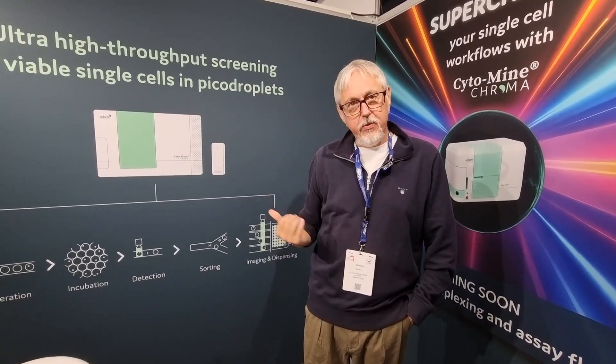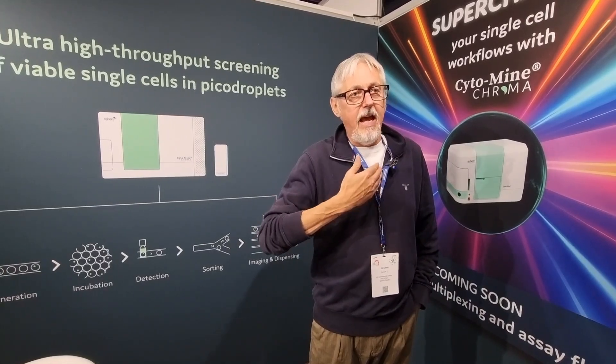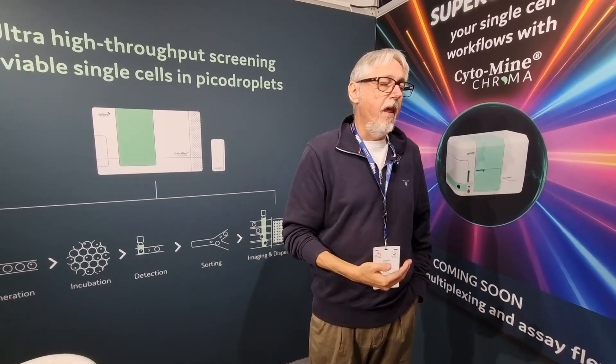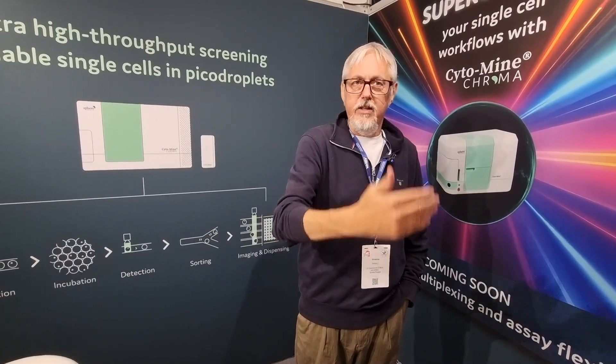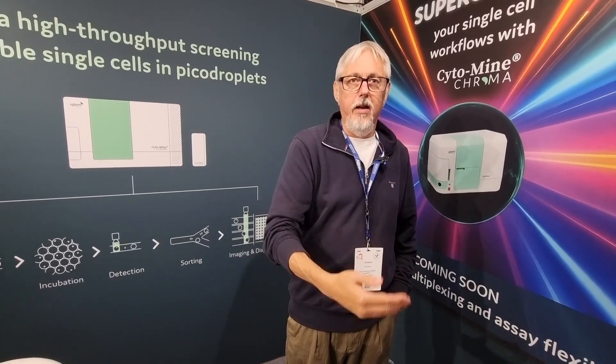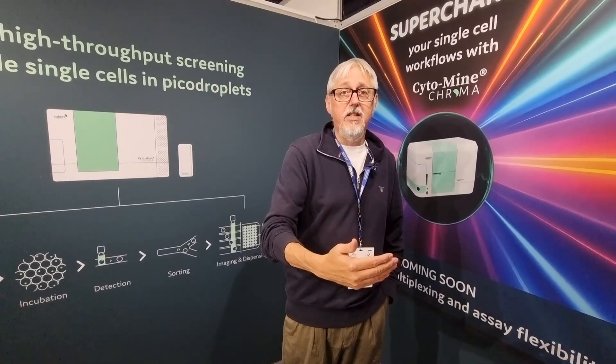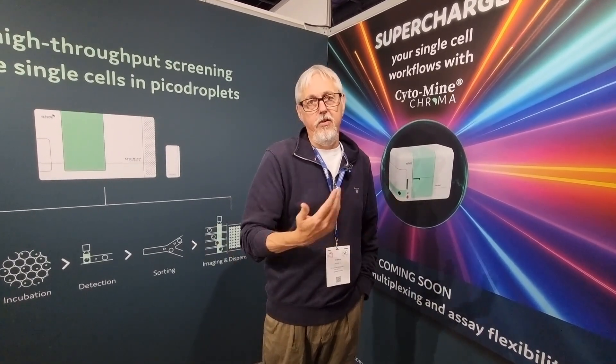So the original Cyto-Mine has two color channels — it's a red and green fluorescence detection system. With the Chroma, we're adding additional channels, so it's going to go to four color, four laser, four PMT. And really, that will just enhance the flexibility of the system and give our customers much more choice in terms of the applications they'll be able to run on.